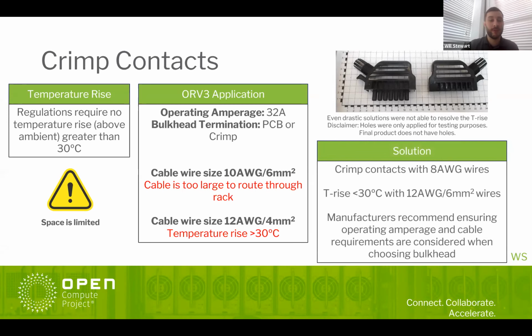How we were able to solve this actually wasn't on the cable side, but on the panel side. We went with crimp contacts with 8 gauge wires, which allowed more material for the electricity to flow through and kept the temperature rise down—again beneath 30 degrees C—while still using 12 gauge wires on the cable, which allows for easier routing through the rack. One thing to note is that we did use crimp contacts to fix this situation.